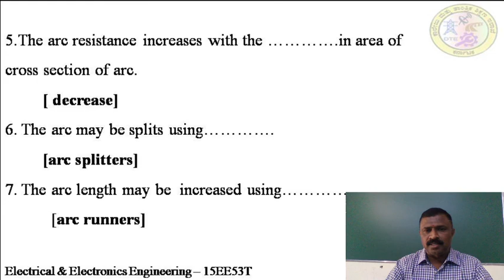Next, the arc length may be increased by using dash, that is arc runners. For both these arc runners and arc splitters, the resistance R is directly proportional to L and inversely proportional to area of cross section. So we are using both these arc runners and arc splitters in order to increase the resistance of an arc. Whenever the resistance increases, we call it a high resistance method of arc extinction.